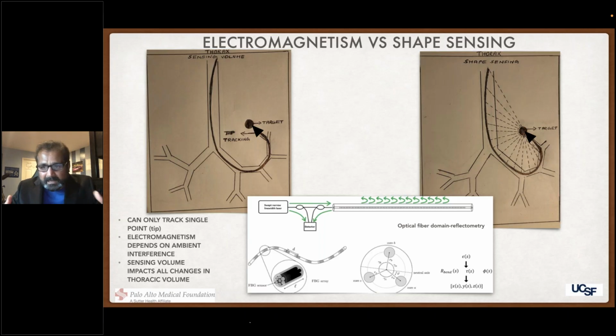So as you can tell, you can use the system in 3 different ways. You can completely use the airway tree and the shape sensing technology by using the lock to path mechanism and just reach the airway regardless of where the green dot is. Or you can use the tip tracking towards the lesion with a navigation platform, and knowing your airway anatomy, you can reach that, or you can use a combination of both. And that actually is a significant advantage as to how you can use the system. And this catheter stress, you're also able to assess.